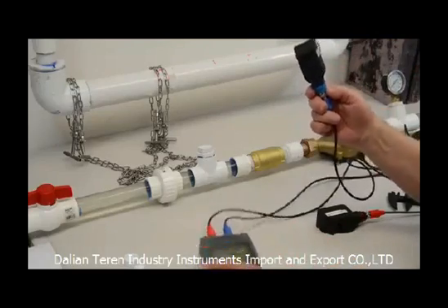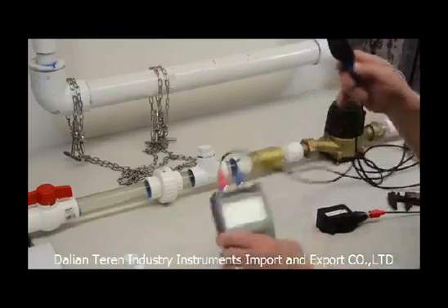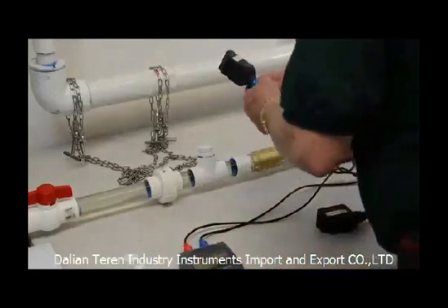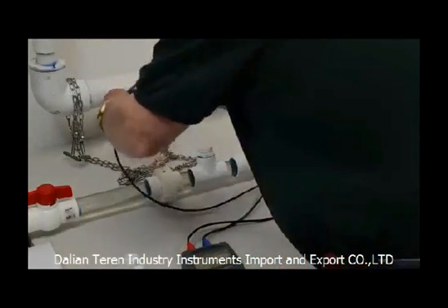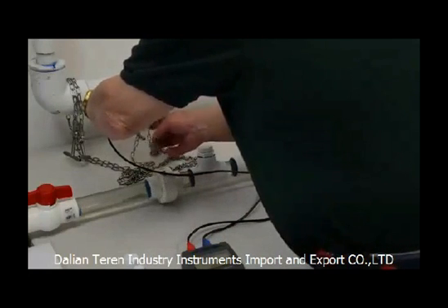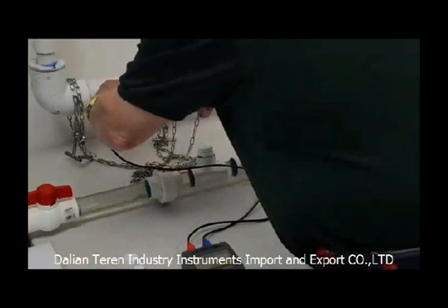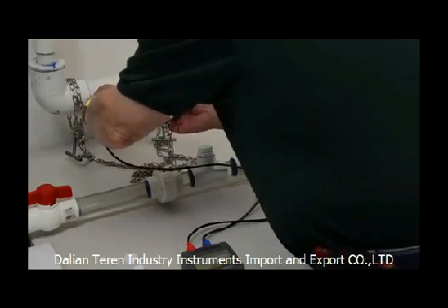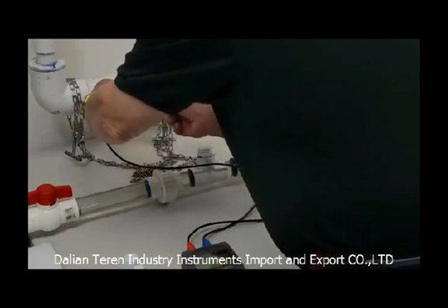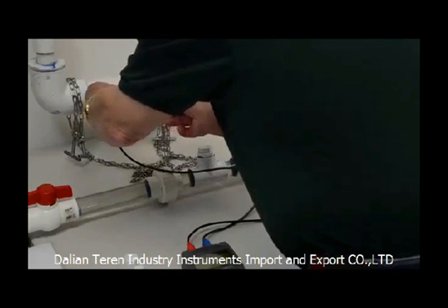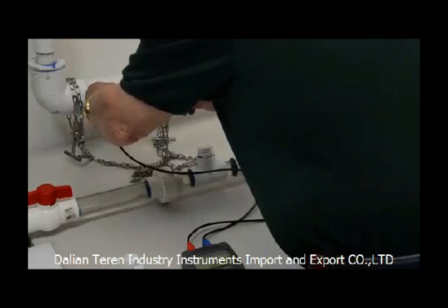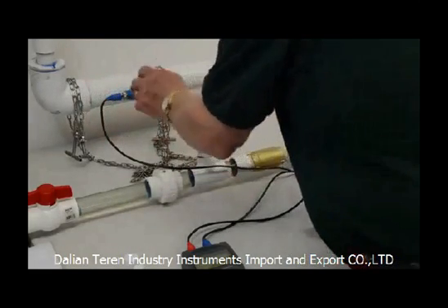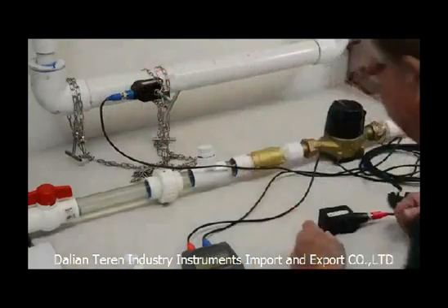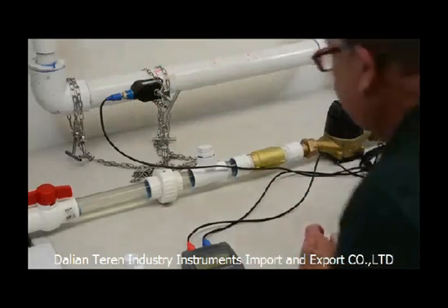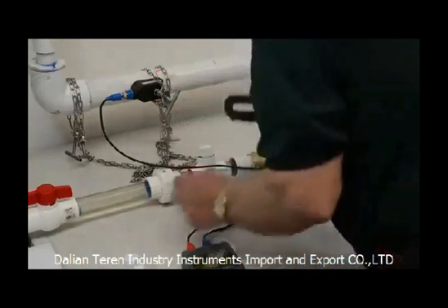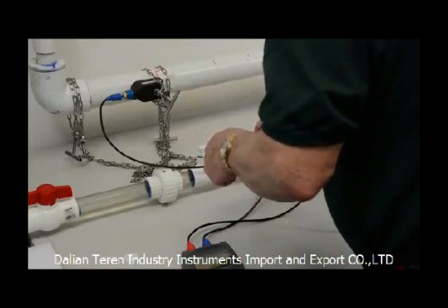In this case, this is my downstream transducer. I can look here and just verify, and I'm going to hook this up, and I've got my cables already in place here. I'm going to attach this, and I'm going to be using the V method as we spoke before. I'm not going to tighten that real tight because I'm going to have to move that to do my spacing. Now I'm going to hook my upstream transducer after I put some Vaseline on here.